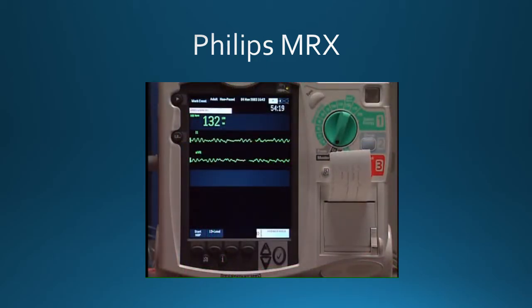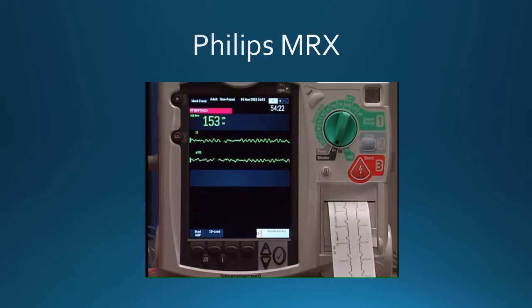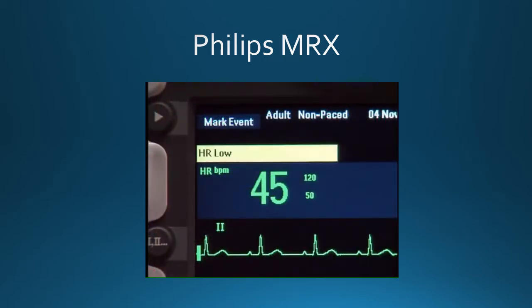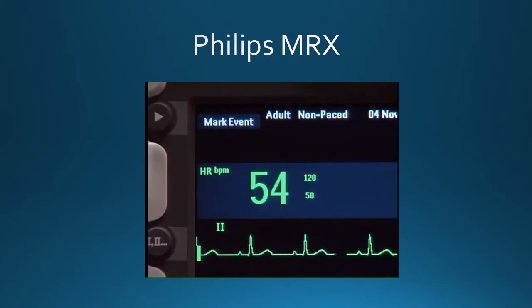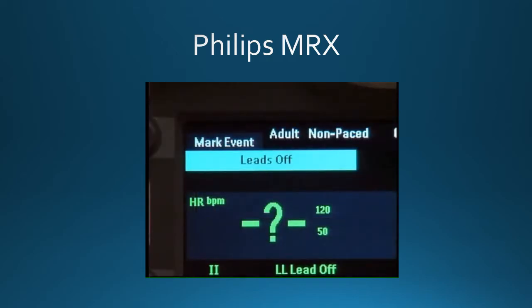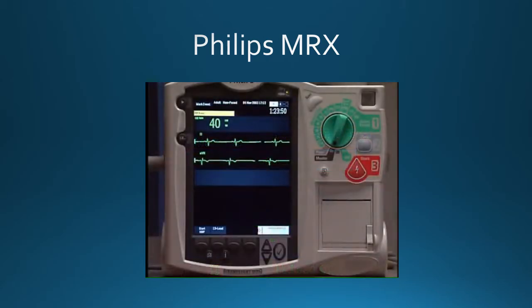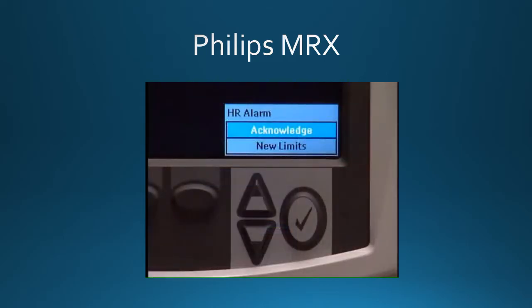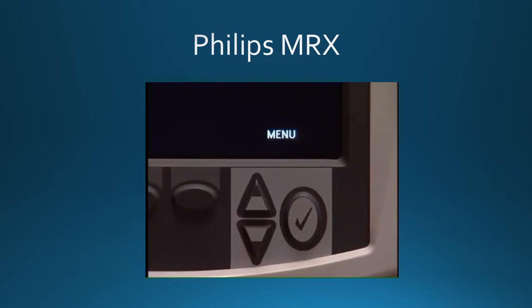Arrhythmia alarms are also categorized as latching or non-latching alarms. With a latching alarm, visual and audible indicators remain present until they are silenced and acknowledged, regardless of whether the alarm condition still exists. With a non-latching alarm, visual and audible indicators disappear when the condition no longer exists. Inops indicate a device problem or error condition, such as this leads off message, and they appear in this cyan background and sound like this. To silence active alerts, you use the menu select or the navigation buttons. Once the condition is corrected, press the menu select button to acknowledge the alarm.